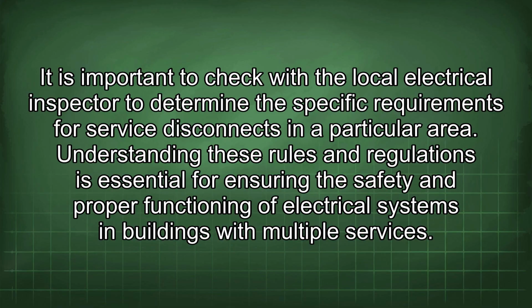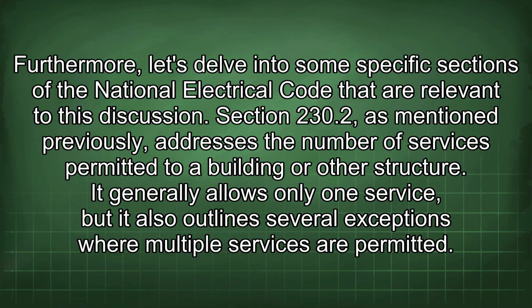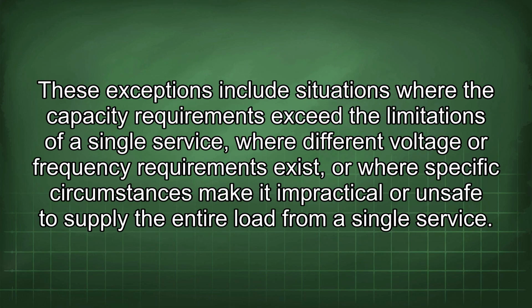buildings with multiple services. Furthermore, let's delve into some specific sections of the National Electrical Code that are relevant to this discussion. Section 230.2, as mentioned previously, addresses the number of services permitted to a building or other structure. It generally allows only one service, but it also outlines several exceptions where multiple services are permitted. These exceptions include situations where the capacity requirements exceed the limitations of a single service, where different voltage or frequency requirements exist, or where specific circumstances make it impractical or unsafe to supply the entire load from a single service.